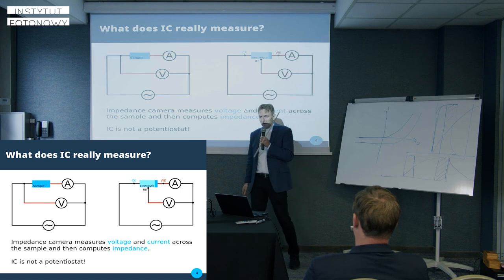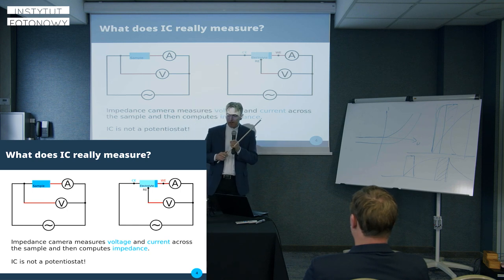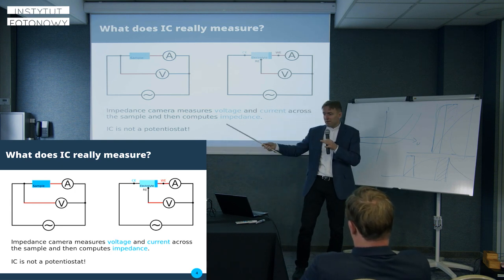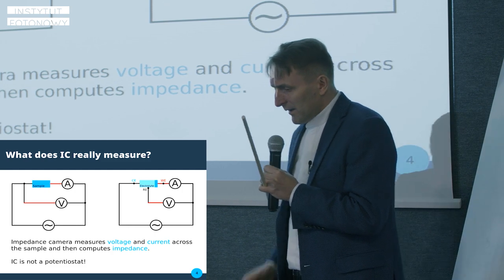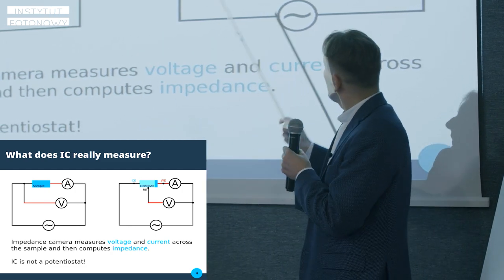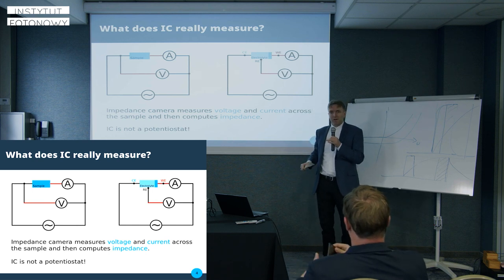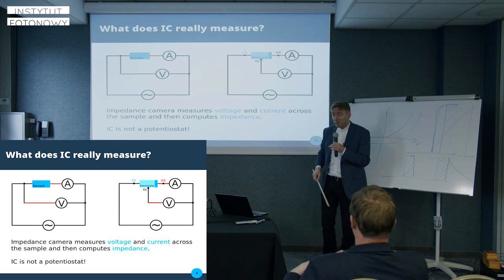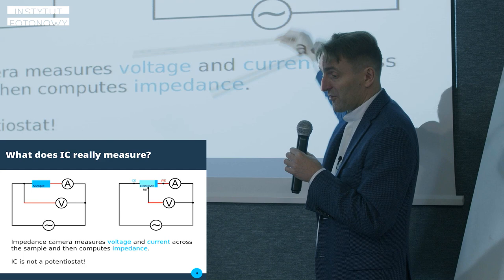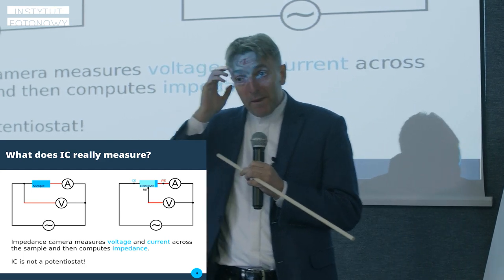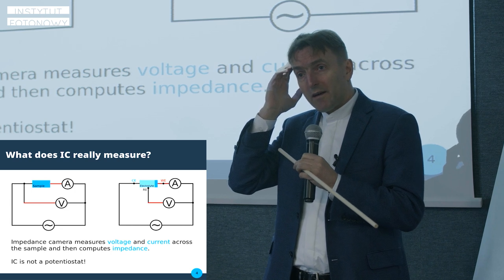The currents measured in the three-electrode setup are way lower than in the two-contact case. For the measurement, the device gets bigger because it is attached to a sample chamber — you need to shield the sample from ambient electromagnetic fields and other things. It may look like you have a potentiostat, but it is not a potentiostat. There is no internal stabilization mechanism that would keep some voltage constant, although you can shift the applied voltage up and down if you wish.